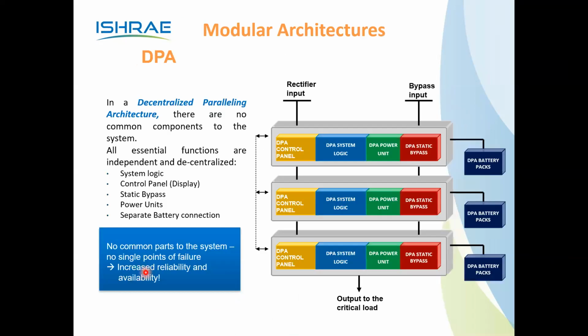And this is how the architecture will be. Now, again, the same concept. This technology uses three modules of 40 kilowatt to support an 80 kilowatt load. Here you can see each module has its own components: control panel, logic, rectifier, inverter, static bypass, as well as the battery. Battery is also possible as common as well as individual, depending on the space availability and the budget of the customer. But module wise, it's a true modular, no common components, no single point of failure.